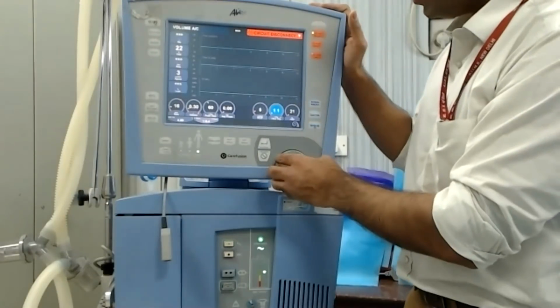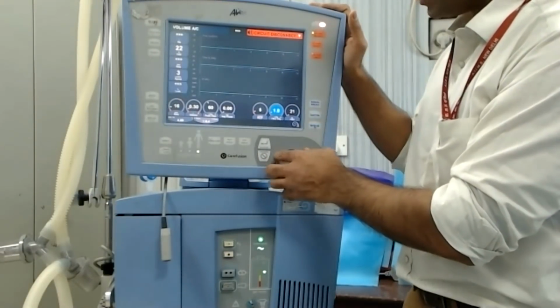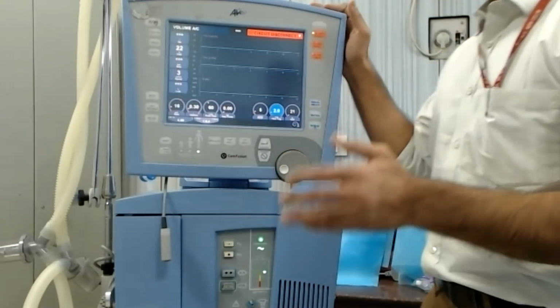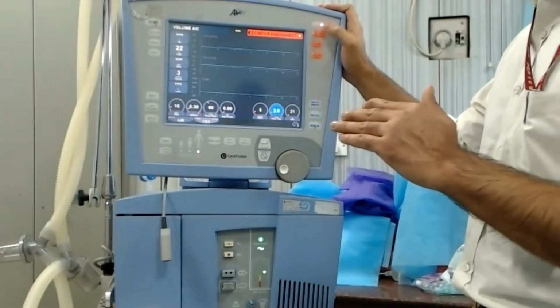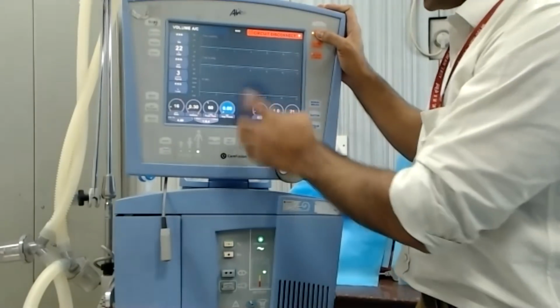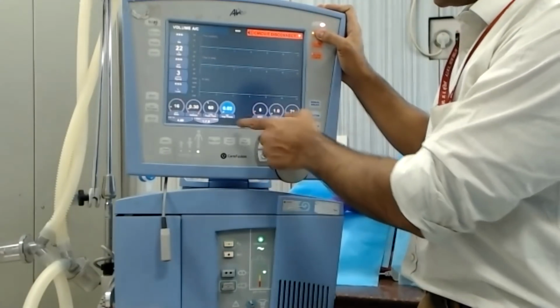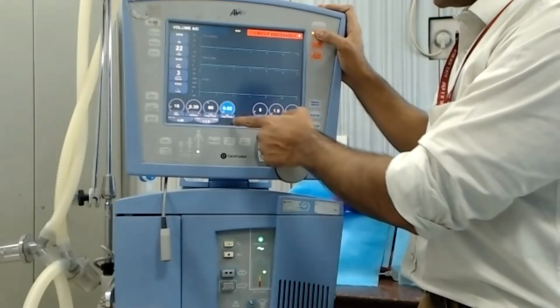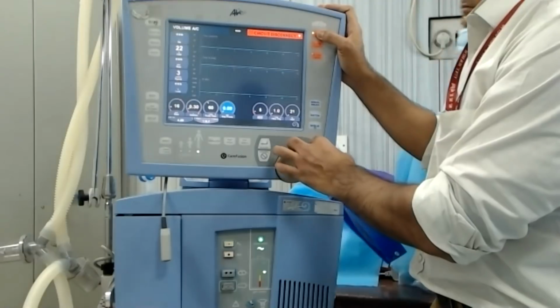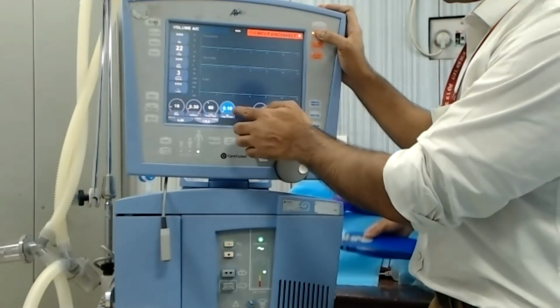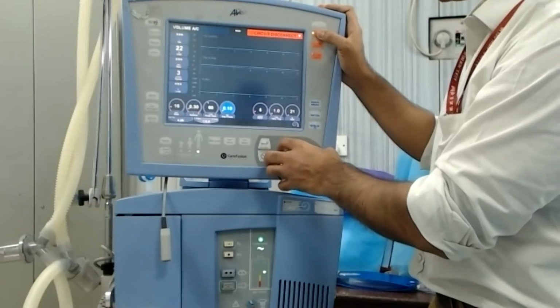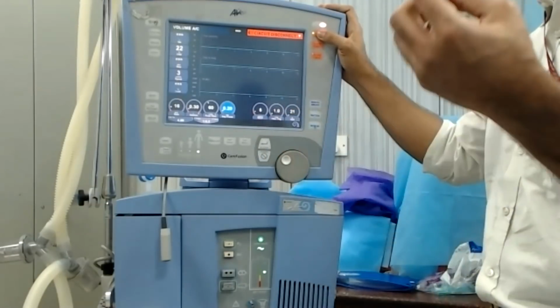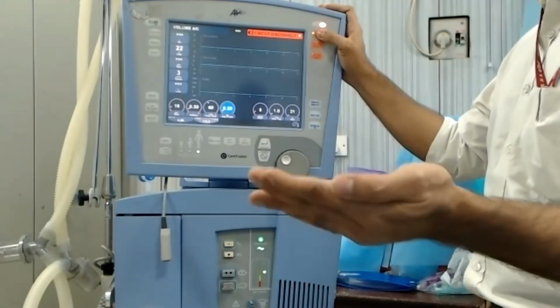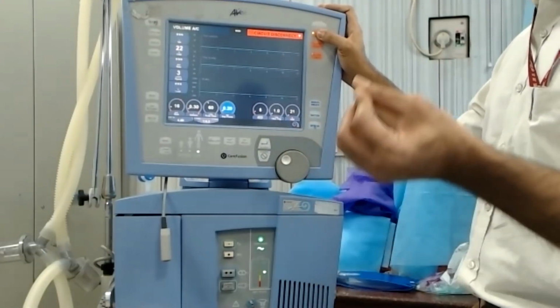This is the flow trigger. You can use flow or pressure trigger, whatever you have in your ventilator. They both work fine in present day ventilators. This is the inspiratory pause, which I was talking about. Keep it around 1 second, then you can keep your pause as 0.1 second or 0.2 second. By doing this in a case of ARDS, you will inflate the lungs towards the end of inspiration. It will help in generation of better mean pressure, better oxygenation.